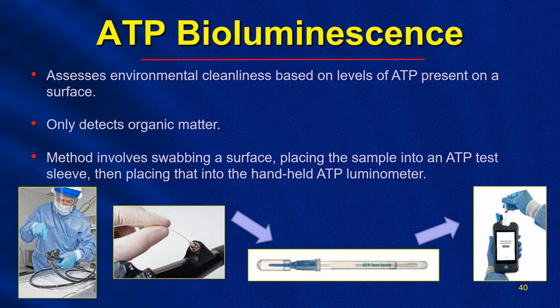This method is carried out by swabbing a surface, inserting the sample into an ATP test sleeve, which contains the luciferin. That reacts to oxygen, and then it's placed into a handheld ATP luminometer. When it's placed into this device, light will be generated from the reaction, and the luminometer will measure the amount of light and give you a quantitative result of the amount of soil left on a particular item. So the higher the number, for instance, if you have a surgical instrument that you want to test to make sure it was cleaned properly, you can get a number which is acceptable or not acceptable. If the number is too high and not acceptable, all that means is that item, that instrument, should be cleaned again and tested again before sending out for final sterilization or high-level disinfection.